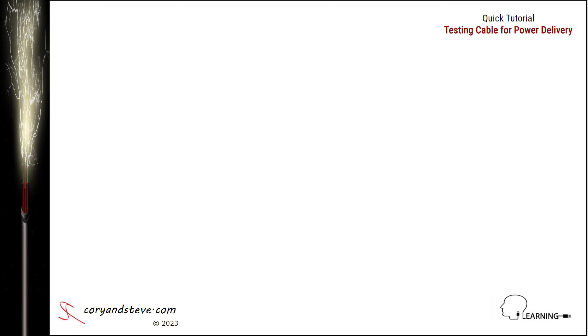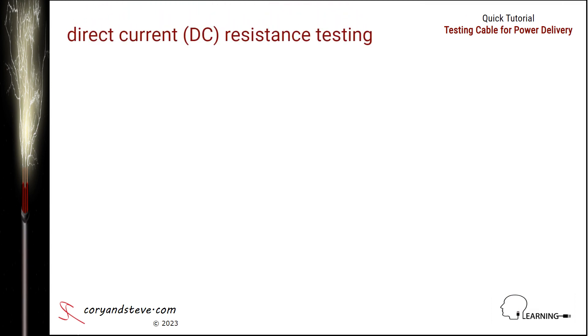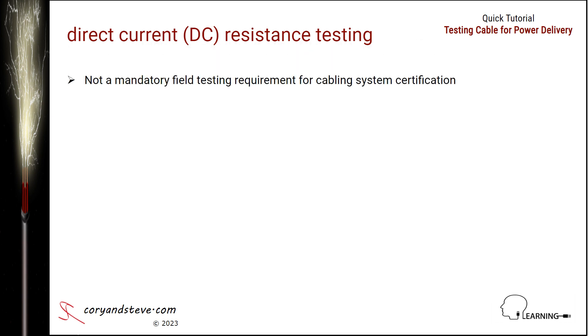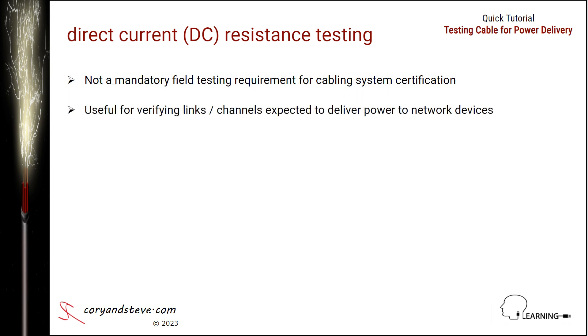Let's begin with an overview of the direct current or DC resistance testing required for this type of verification. It must be emphasized that DC resistance testing is not a mandatory field testing requirement for certifying a cabling system as category compliant. However, any organization that wants to verify whether or not its cabling links or channels can handle power delivery can do so by performing this type of testing.